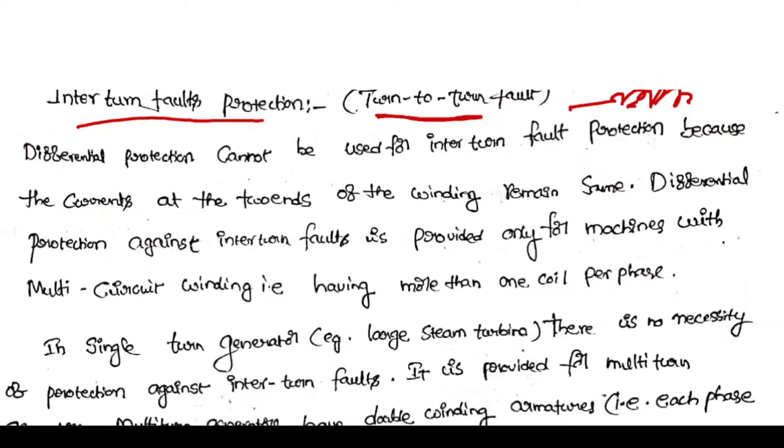Merz Price circulating current scheme, that is differential protection, cannot be used for inter-turn fault protection because the currents at the two ends of the winding remain same. The two ends of the winding will be the same.